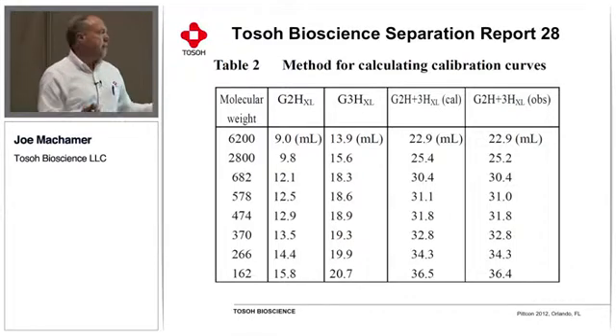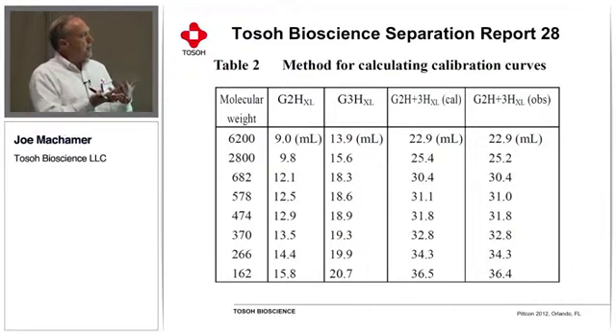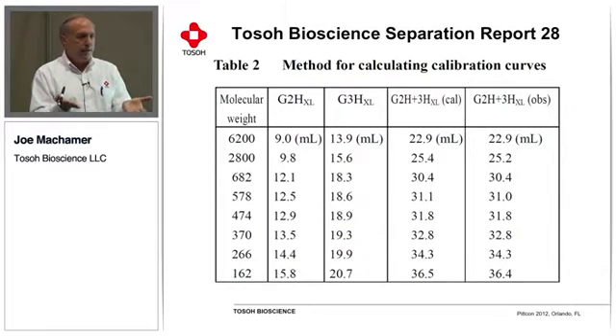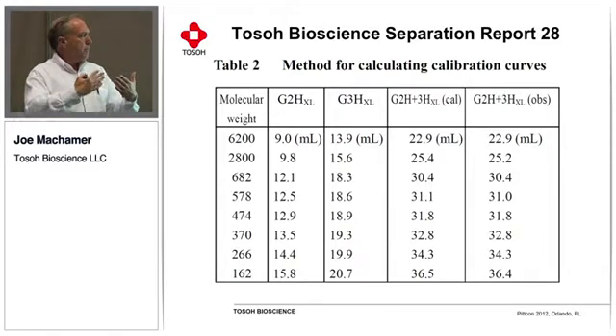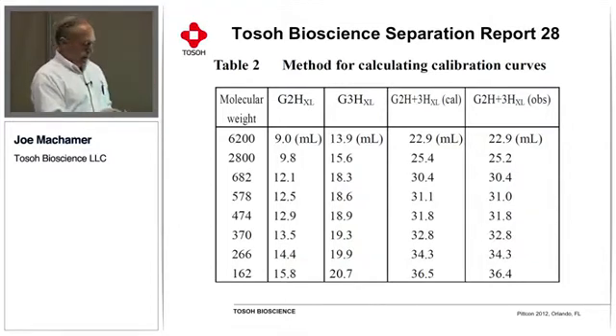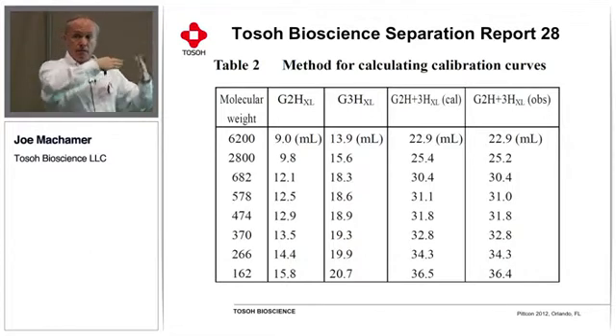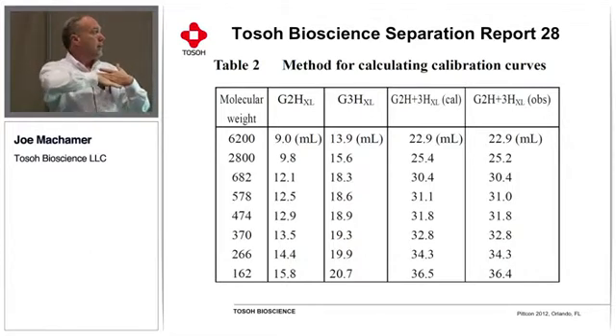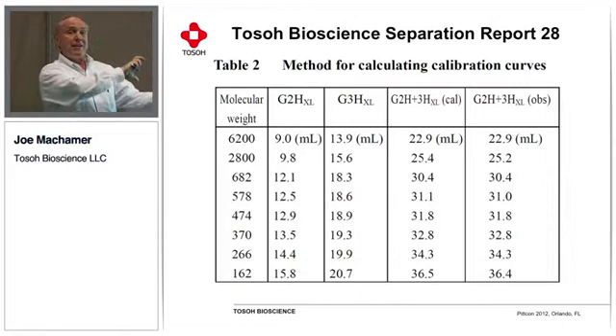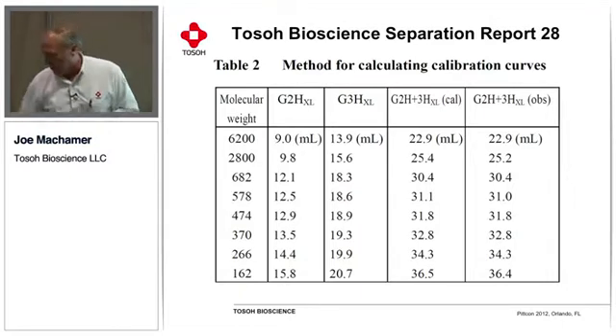So the idea here is basically the separations with GPC are very, I don't know, mathematical is the right word. Essentially you can look at a calibration curve, and if you can come up with a scheme to mathematically add those calibration curves to each other, that goes a long way towards predicting how it's going to behave when you actually run the sample. So the combination of me coming across this chart and having a need to look at how different calibration curves compare, comparing different types of columns to each other, that's what the motivation was.